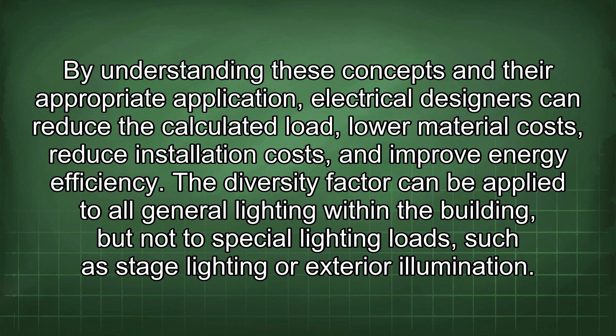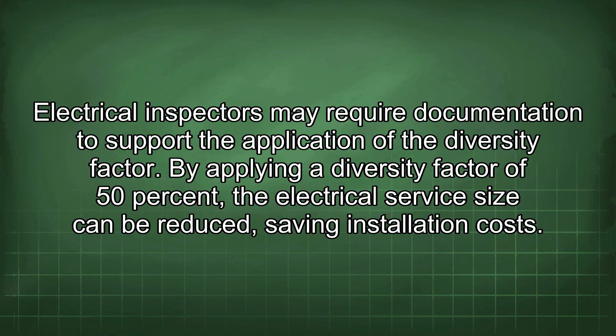The diversity factor can be applied to all general lighting within the building, but not to special lighting loads, such as stage lighting or exterior illumination. Electrical inspectors may require documentation to support the application of the diversity factor. By applying a diversity factor of 50%, the electrical service size can be reduced, saving installation costs. The NEC is a minimum standard, and local building codes may have additional requirements or restrictions. Always consult with a local building inspector or qualified electrician for specific guidance.